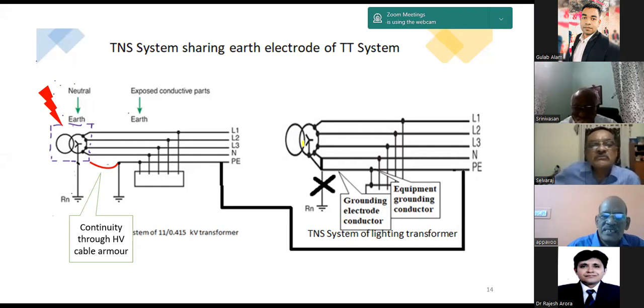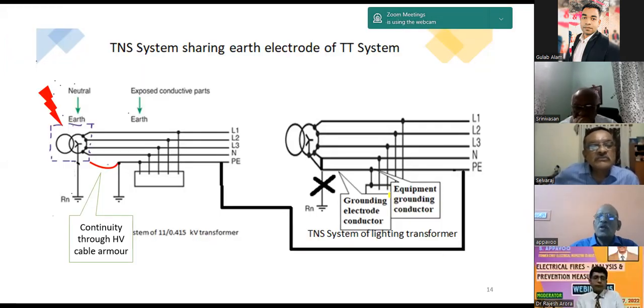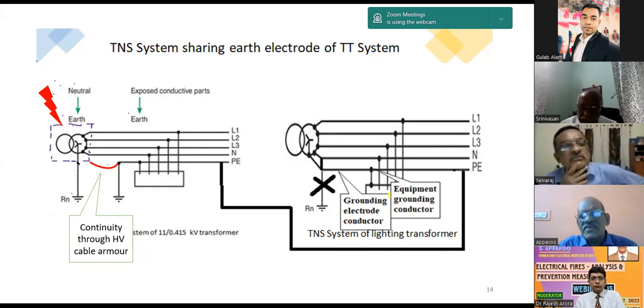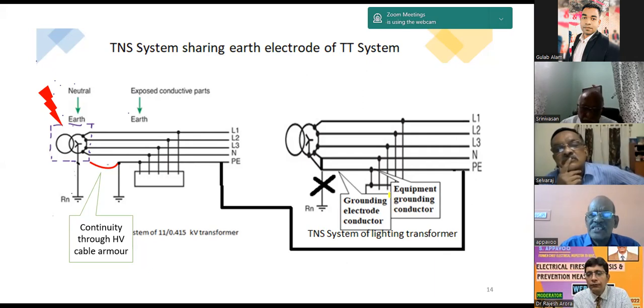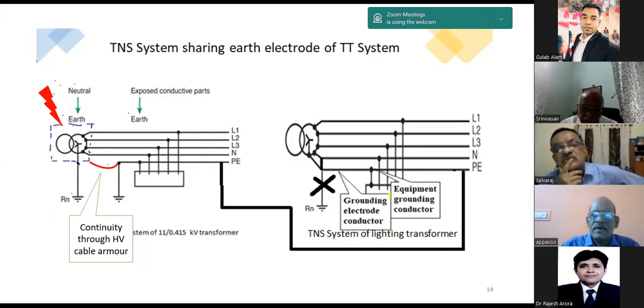lighting transformer. When we measured the temperature of the lighting transformer, we found that there was no problem with the insulation resistance, and the heat rise was just 80 degrees centigrade. It was not so heavy, it was not so high. And we also found some cotton stuff burning inside the lighting transformer. It was not accessible, it is rightly placed in the corner of a maintenance personnel room. Nobody can enter easily. As a result, it was not possible to open the terminal block or the door frame of the lighting transformer to insert any incendiary means of light. That possibility is ruled out. Also, there is no communication of fire between the transformer and the cable trunks beneath the transformer.